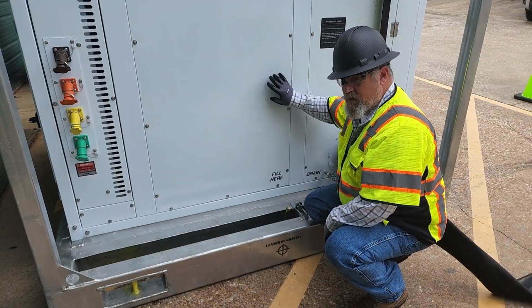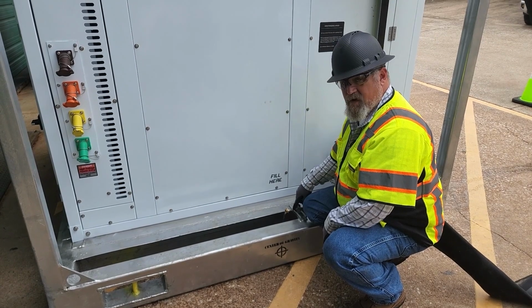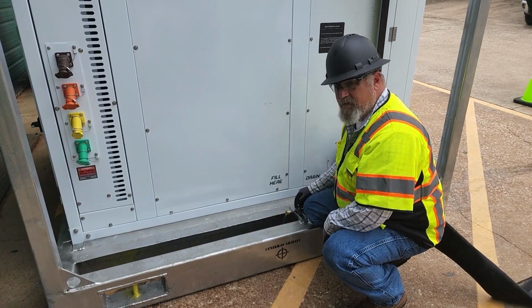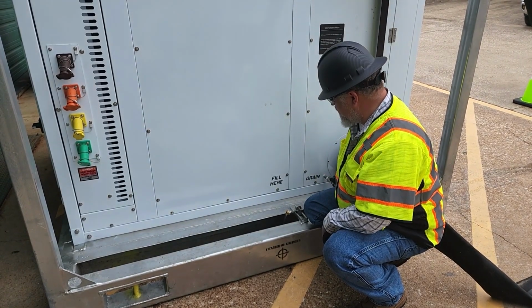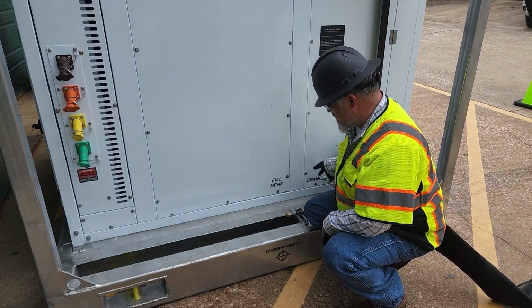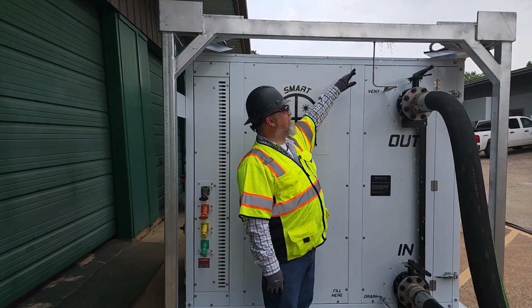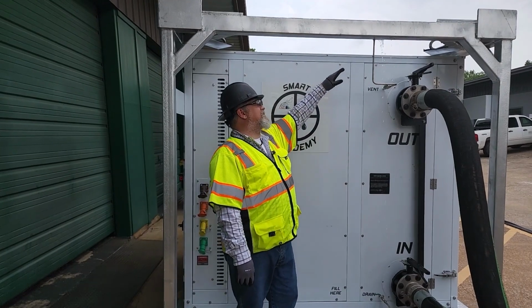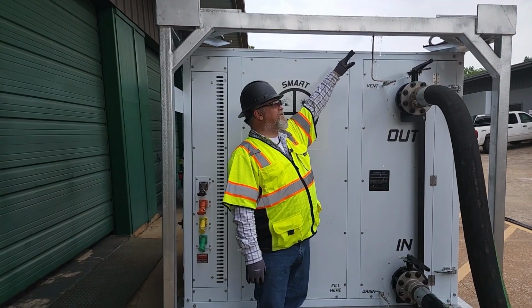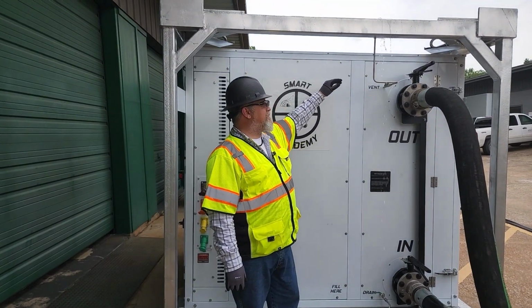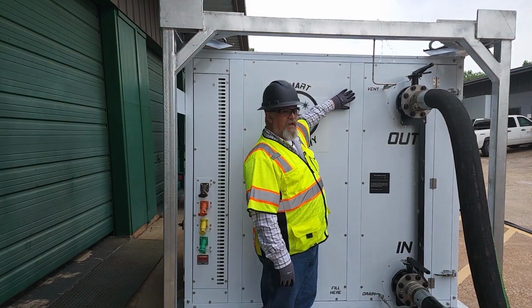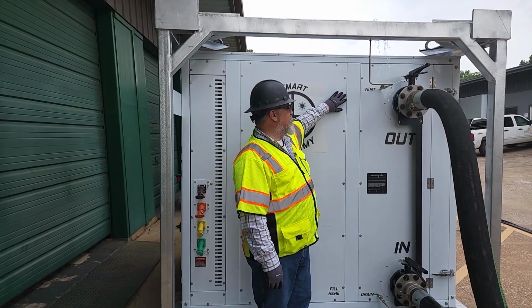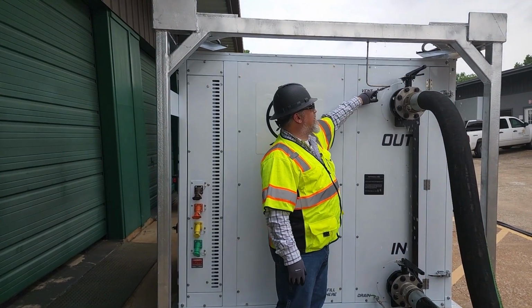All right, now you can see on our air handler here, our lowest vent is now draining water. I've let it run for several seconds, so now I'm going to go ahead and close this ball valve. All right, so my top vent here has started pouring water. Now at first it was just kind of gurgling, but now it's a nice clean stream. So it should mean that I've removed all the air from this air handler. So I can go ahead and shut this off.